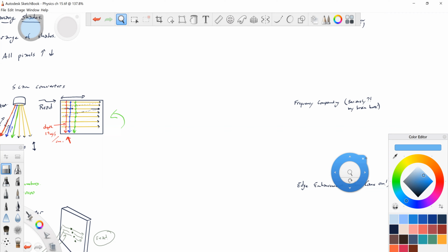You would think we'd be able to, but we cannot change time gain compensation after the fact. You know what, I bet on the most modern machines we can, but on most machines we cannot. So let's just stick with that. We cannot change time gain compensation. So it is a pre-processing. However, we can change gain, overall gain. We can change the entire screen's gain, but we cannot change the curve of the gain.